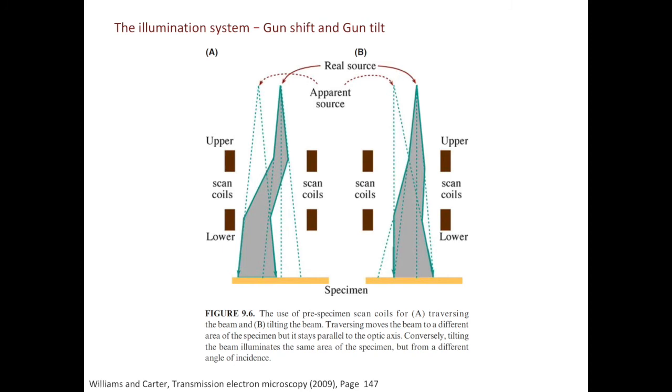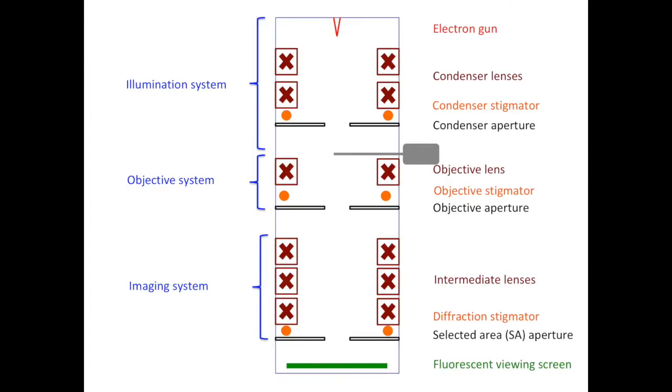In order to correct them, we need to do Gun Shift and Gun Tilt. The fundamental idea of the Gun Shift and Gun Tilt alignment is to make sure the electron beam travels along the optical axis of the lenses. How do we do Gun Tilt and Gun Shift? Let's come back to the TEM sketch. So we have the Gun Deflectors to do that. Similarly, in the objective system, we have the Beam Deflectors to do Beam Shift and Beam Tilt.